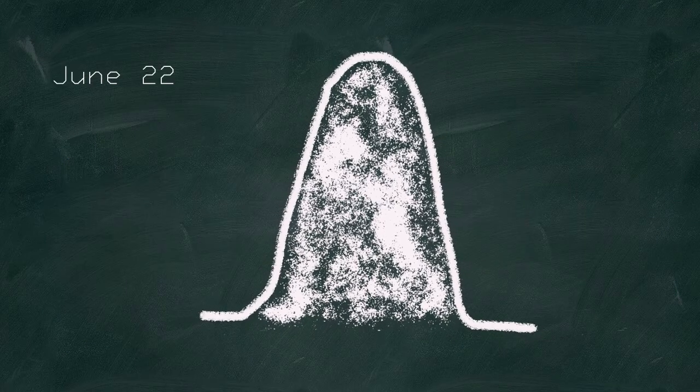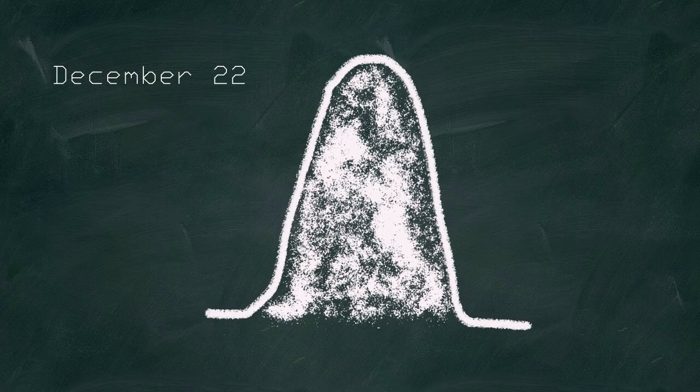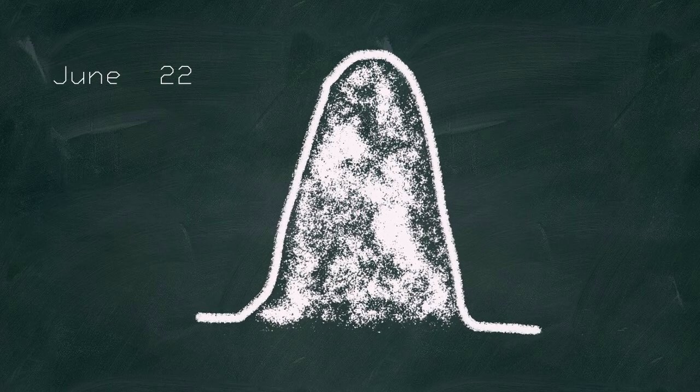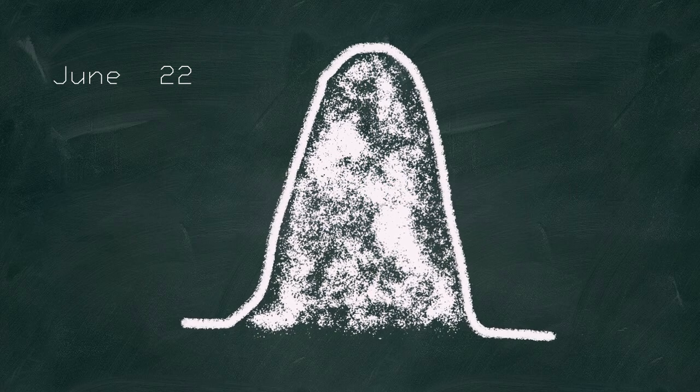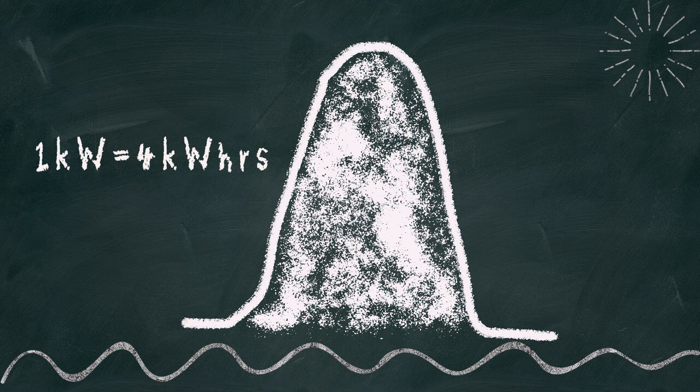When you graph a panel's output, it is a bell-shaped curve that seasonally changes in amplitude and width. The area under the curve is the power output. On average, for each kilowatt of installed panels, you'll get 4 kilowatt hours of power on a daily basis. 10 kilowatts installed, 40 kilowatt hours of solar power generated.